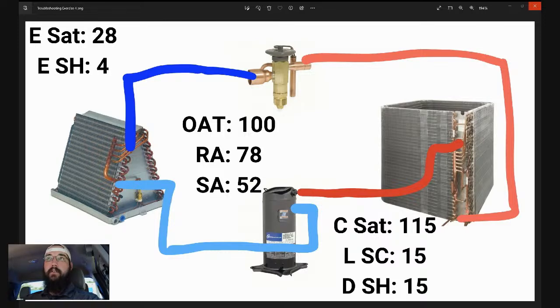Above 28, so above 30 degrees, 30 to 32, you might not even ever ice over. You're right there at a tipping point where it's not quite cold enough to get a hard freeze on the coil unless it actually ran all day and nonstop. Then you might have an icing issue. But at 28, you'll start to see that. And running a 4-degree superheat at a 28 saturation, those two things together, that coil is going to ice fairly quickly. It's got a lot of good refrigerant in there at a really cold temperature. That liquid just sitting through that whole coil boiling off is going to cause a lot of icing pretty rapidly. So that would be my expectation here.